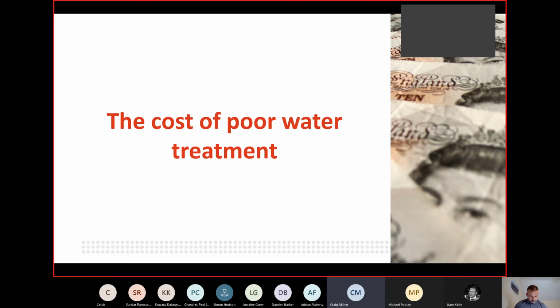Sorry, let me get my thoughts straight. Cost of poor water treatment - poor water treatment can be worse than no water treatment. If you don't put enough in, it'll be protecting a certain part of the system, but water's got X amount of corrosive power, and if part of the system's not protected, all the corrosive power in the water will be attacking a small section of the pipework.